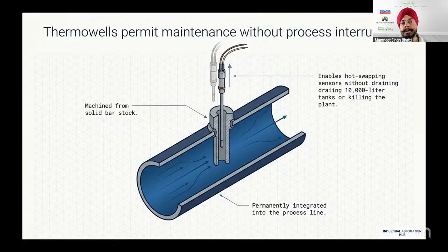If I have to calibrate a thermocouple, I have to bring it out and then calibrate it in a known temperature chamber. So I have to bring it over there. If I don't bring it over there, I will not be able to calibrate it. So sometimes we have to remove those sensors.